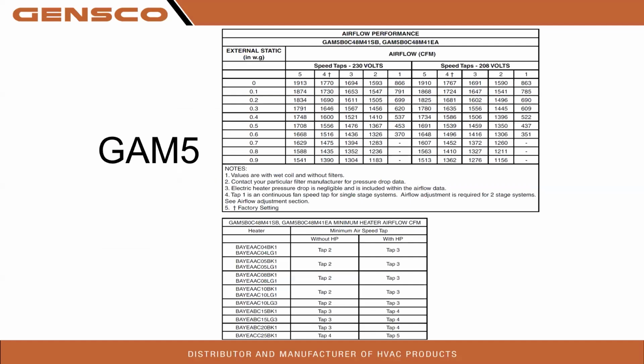GAM5. Again, all these charts are kind of the same. So that's what we wanted everybody to be aware of, all these service facts. You're going to have an external static. So you're going to take your external static and compare it to whatever speed tap you're on. There's usually a default that's marked. So this one's default speed tap 4, at 0.5 you're at 1556 CFM.